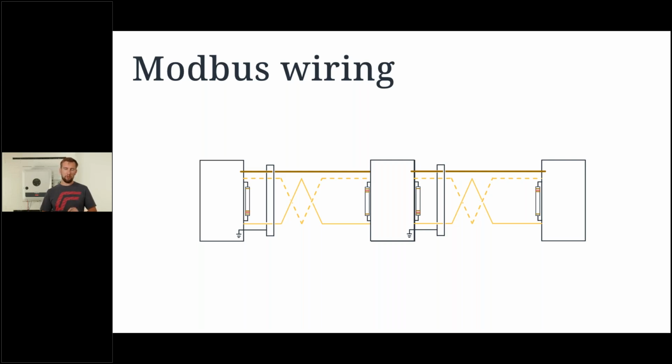in the middle. Logical solution, let's remove that termination resistance from all the devices that are in the line and only leave a termination resistance at the devices at each end of our serial connection.